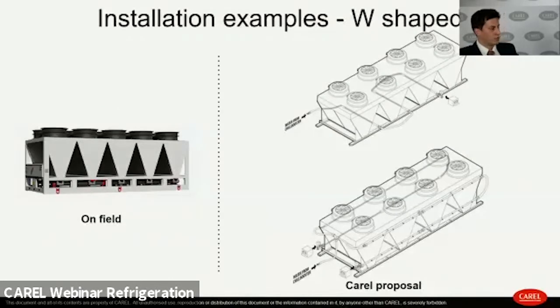One last possible configuration is the W-shaped coil. We have a double V coil heat exchanger, and again, we can have two possible layouts. The serpentine one on the top, so we can pass the manifold through the V coil, or a more standard one, again, installing the manifold on the external surfaces.